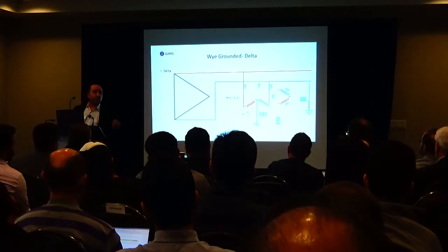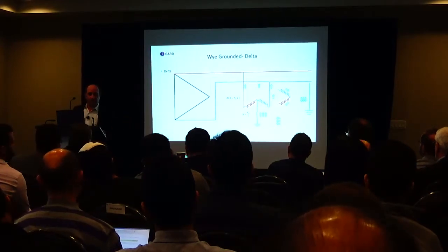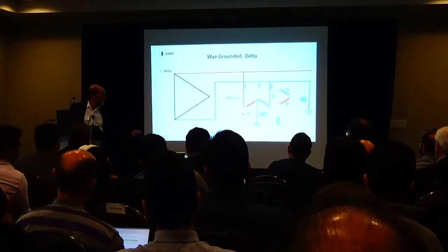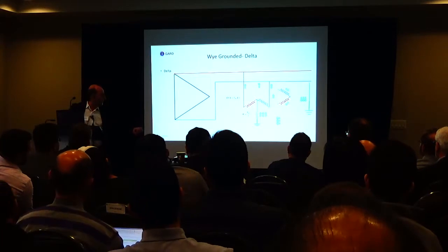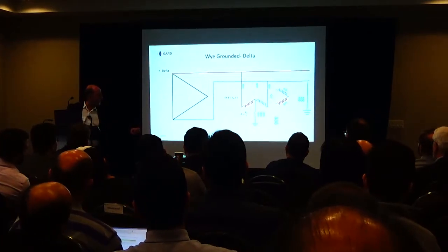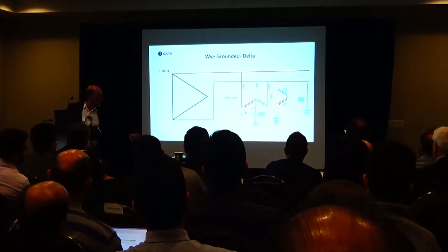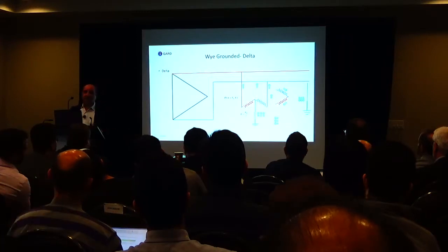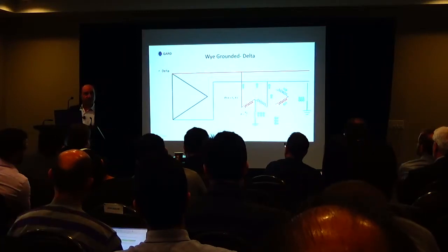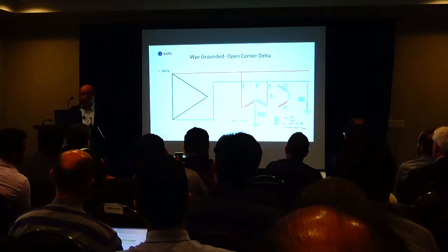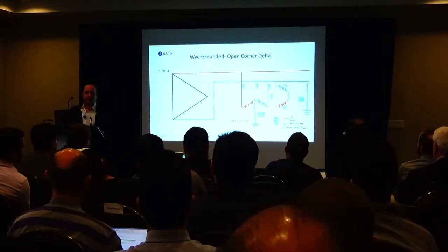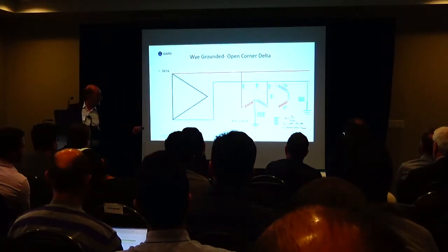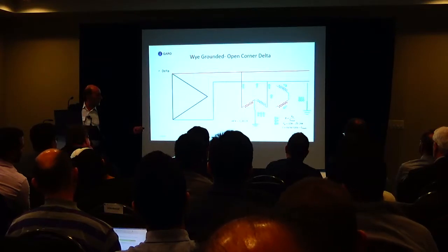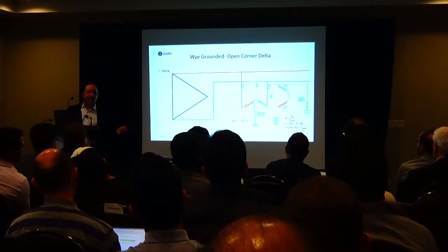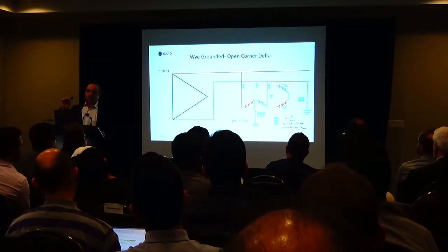You can also use a Y-grounded delta. With a Y-grounded delta, you have single-phase transformers. They could be 4160 to 120. You have a ground fault, and the current returns back this way. Or you can have a Y-grounded open corner delta. What we've done here is opened up one of the corners, put a resistor in there, and that resistor impedes the fault current.